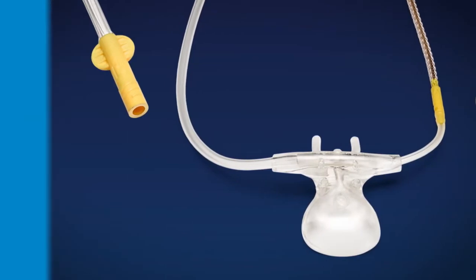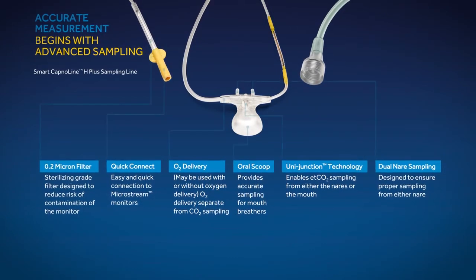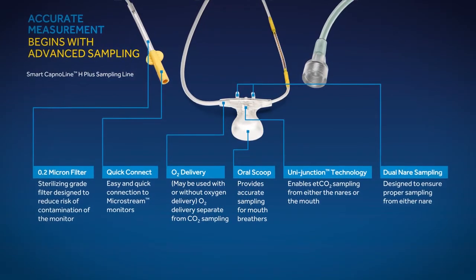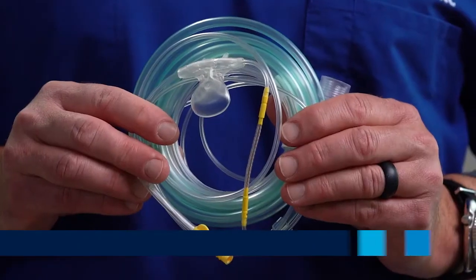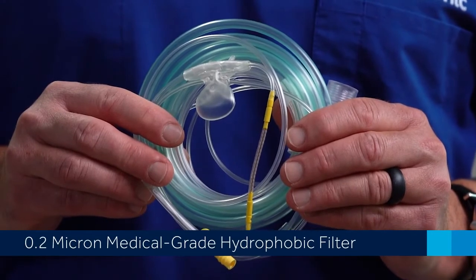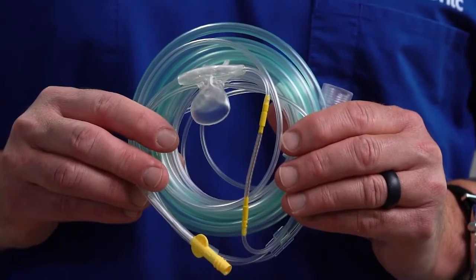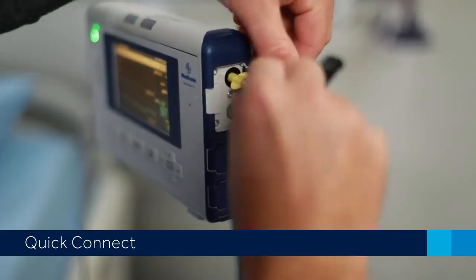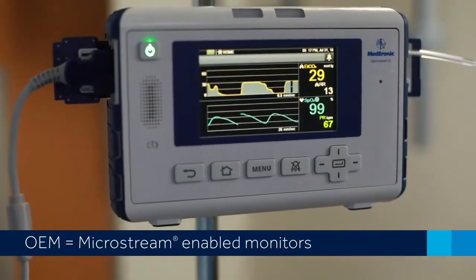The sampling line provides sampling from both nares and the mouth, even at low tidal volumes, with exclusive uni-junction technology. The universal oxygen tubing is for any oxygen connector or direct attachment to any oxygen flow meter. The filter line sampling line is engineered with micro-bore tubing and a 0.2 micron medical grade hydrophobic filter for fluid ingress protection and to help reduce the risk of contamination to the monitor. Quick Connect enables easy and quick connection to the Capnostream 20P and the Capnostream 35 monitors, plus many MicroStream technology enabled OEM monitors.